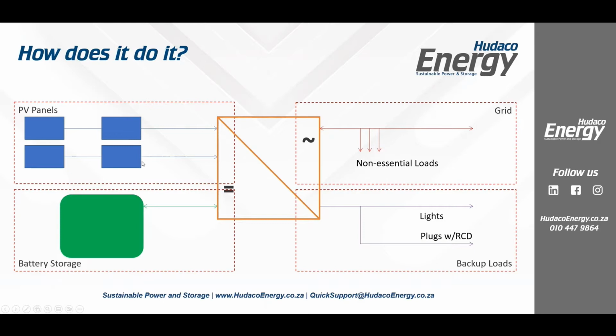So in a case where I'm producing 10 kilowatts, let's say my batteries are fully charged. It's reached 11 o'clock in the morning. My batteries are charged. My essential loads are pulling 4 kVA for whatever reason. I can still at the same time push 6 kVA back through here to all of my non-essential loads. So what that means is I'm not wasting power. I'm not curtailing power from my modules. I can run geysers, I can run ovens, I can have my pool pumps turn on, I can have all of these things fire up and run, so long as I've got voltage there.